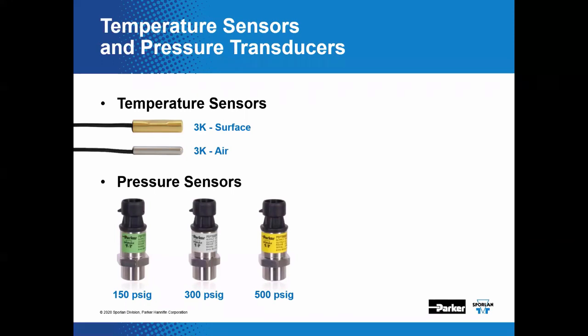Anyway, the appropriate pressure transducer should also be selected based on the pressure range seen in the system. As you can see here, we've got a few examples, 0 to 150 PSI gauge, 0 to 300, and 0 to 500. There are other models as well available for specific applications. These newer models can be easily identified by these fancy color-coded labels that are on them and the nice heavy-duty stainless steel construction. That's exactly right. Cool.